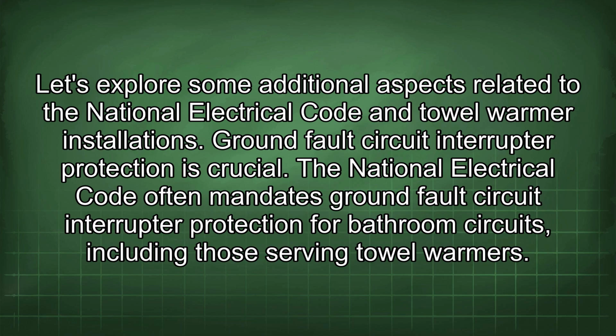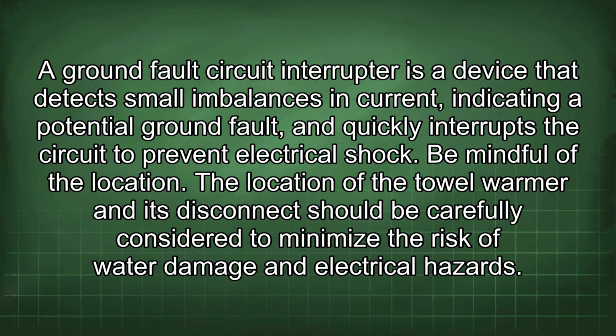Let's explore some additional aspects related to the National Electrical Code and towel warmer installations. Ground fault circuit interrupter protection is crucial. The National Electrical Code often mandates ground fault circuit interrupter protection for bathroom circuits, including those serving towel warmers. A ground fault circuit interrupter is a device that detects small imbalances in current, indicating a potential ground fault, and quickly interrupts the circuit to prevent electrical shock.